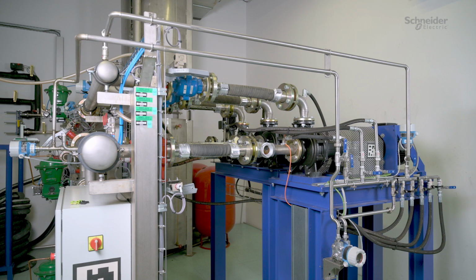Hello! Today we will show you how to manage the pumping systems with ATV600 by displaying the characteristic curves of the pump and its best efficiency point, BEP. This will allow you to monitor the actual operating point of the pump relative to its BEP. You can apply this function to a centrifugal pump or any other pump with similar characteristics. The goal is to demonstrate the embedded features of Altivar Process ATV600.